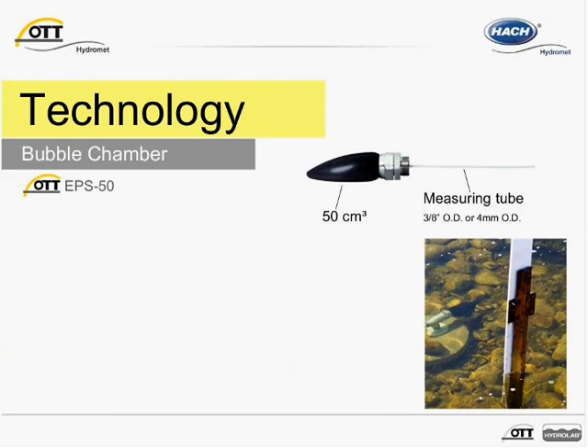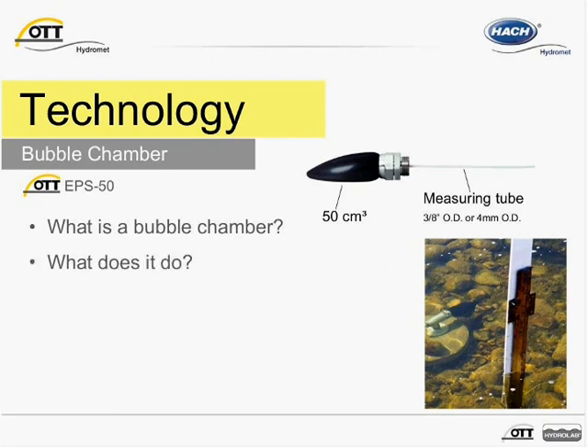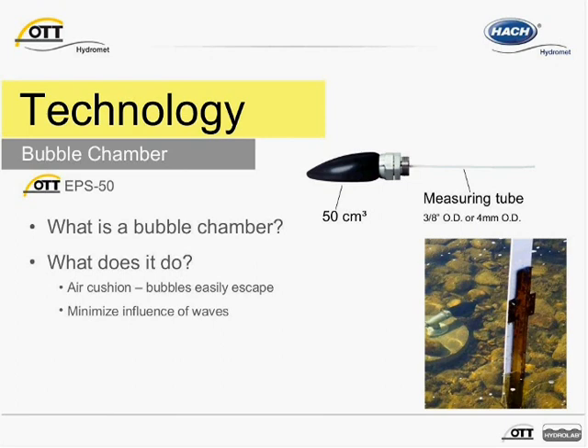You might wonder what a bubble chamber is and what it does. A bubble chamber creates a cushion or buffer that allows bubbles to easily escape the measurement tube when the pressure exceeds the hydrostatic pressure of the water column above the bubble chamber. The bubble chamber shown here is the EPS-50 — a bubble end system with a volume of 50 cubic centimeters. Its deer foot or teardrop design assists with minimizing current pressure effects around the bubble chamber. Bubble chambers also reduce waves near the opening of the measuring tube, minimizing wave influences on measurements and reducing additional data processing. Bubble chambers also prevent water from entering the measuring tube.